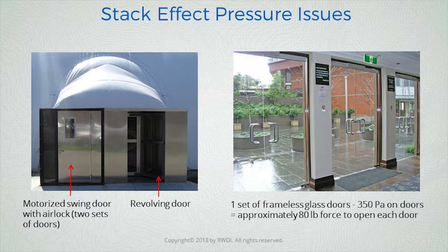It's not architecturally pleasing. The picture on the right is an architectural version of trying to control pressure, but it just won't handle the pressures. The doors will be difficult to open, there'll be lots of whistling, and it'll likely transport some of the stack effect problems into the center of the building.